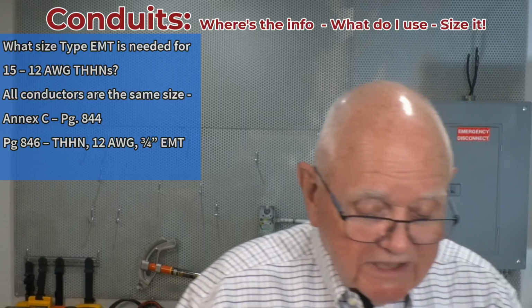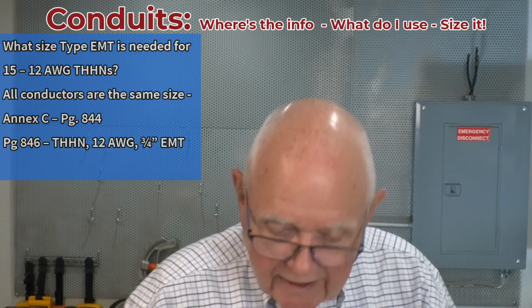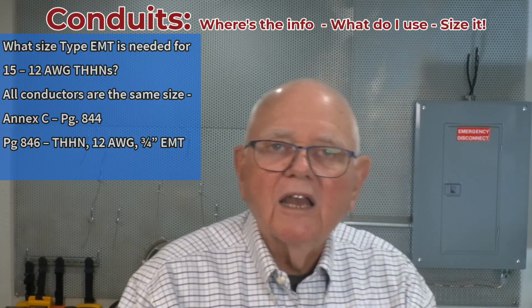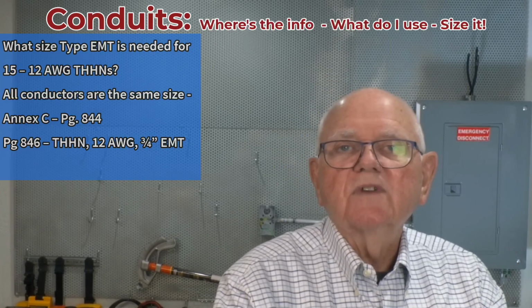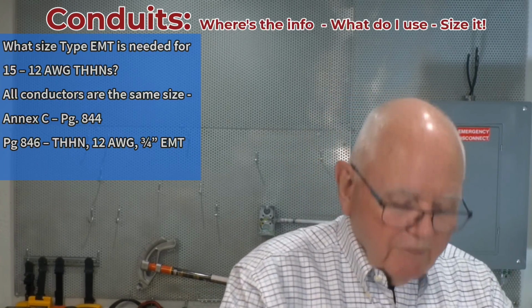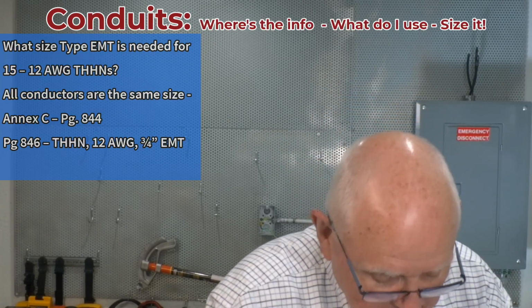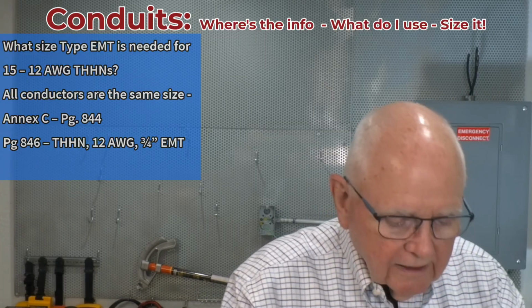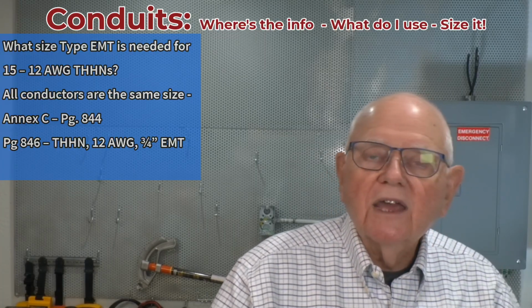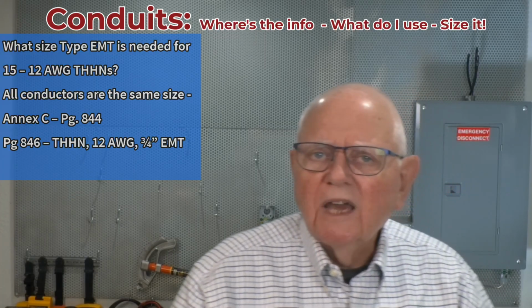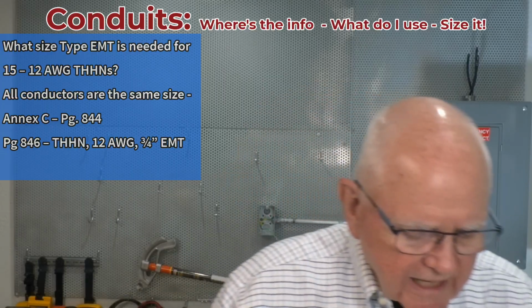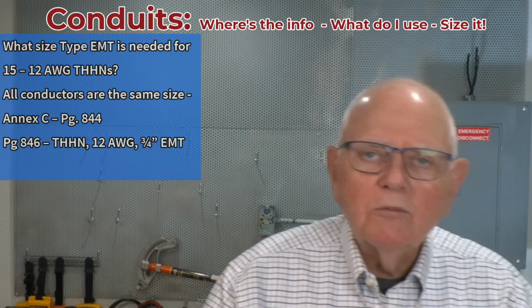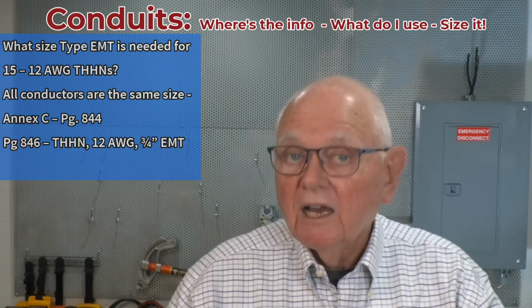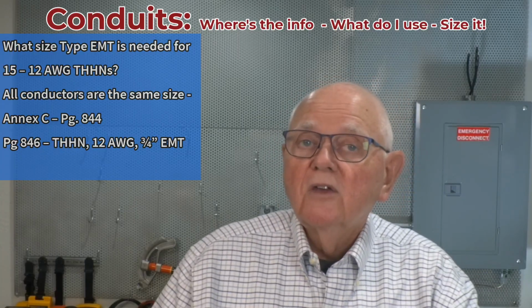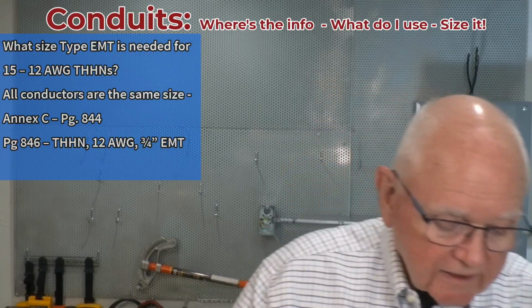So that happens to be table C1. And I look down the left-hand column and I find my different types of conductors. If I go over to page 846, I'll find my THHN in the left-hand column. It's the second grouping down on the left-hand column. THHN, the next column over is my conductor sizes. I said we were using number 12, so I find the number 12 in that second column.